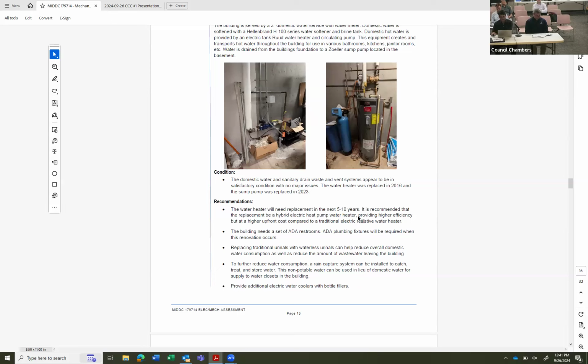Depending on when the design is actually done, we might recommend replacement of it, and a replacement with a hybrid electric heat pump water heater would greatly increase the efficiency. So again, this is an independent system, but it uses heat pump technology to extract heat from the room and use it as kind of a preheat for the hot water system.